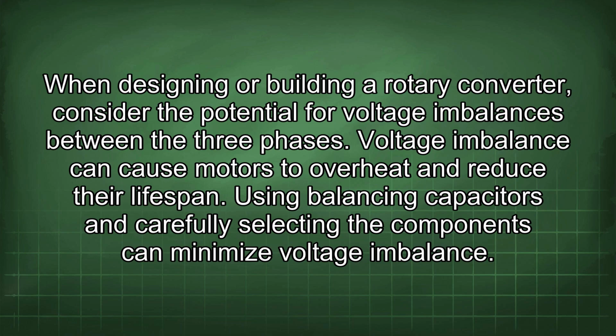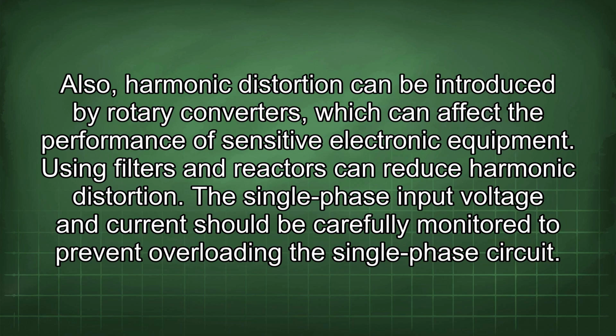Using balancing capacitors and carefully selecting the components can minimize voltage imbalance. Also, harmonic distortion can be introduced by rotary converters, which can affect the performance of sensitive electronic equipment. Using filters and reactors can reduce harmonic distortion. The single-phase input voltage and current should be carefully monitored to prevent overloading the single-phase circuit.